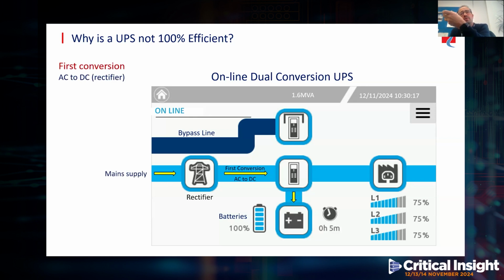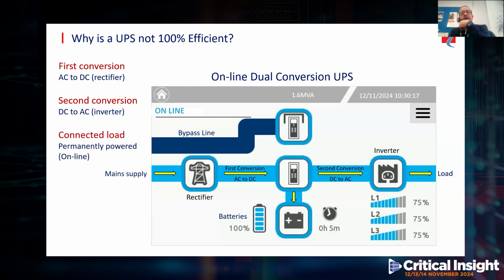Now, the first conversion is the conversion of the incoming AC voltage into DC voltage, and the second conversion is the conversion of the newly created DC voltage back into a clean and stable AC voltage in order to provide the power to the critical load. Now, the term online simply refers to the fact that the load is being permanently powered by the inverter. And basically, it is these power conversions that obviously cause the losses within the UPS and the subsequent heat that is generated.